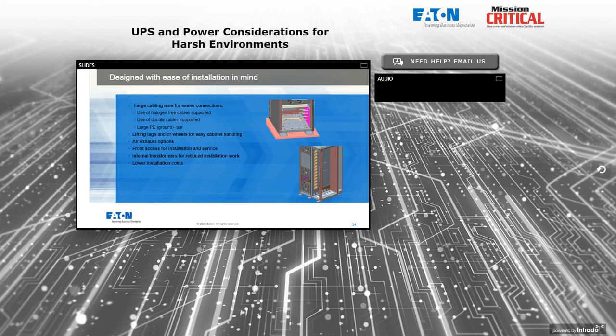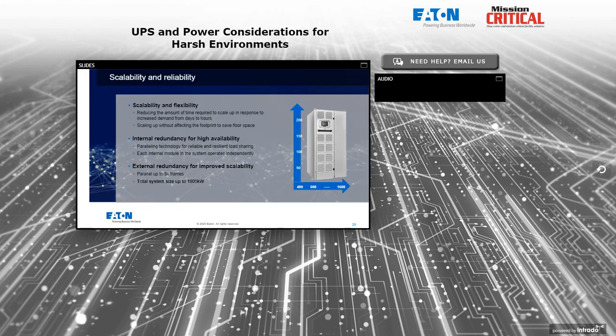Ease of installation still important, just like it is in data center UPSs. Halogen-free cables supported for international applications primarily. Double cabling for double neutraling, things like that, if that's required by the application. We talk about lifting lugs, air exhaust, either from the top or the back, user selectable at the time of order, typically, not usually convertible in the field. Front access for both installation and service. All operations should be able to be done from the front. Internal transformers and anything that helps lower my cost of installation. Having the transformer built into the UPS, for example, is going to be a significant reduction in the amount of pipe and wire that has to be used on site.